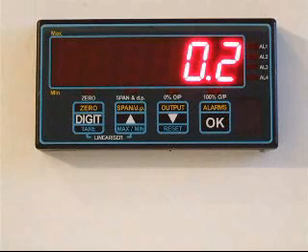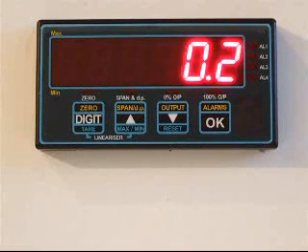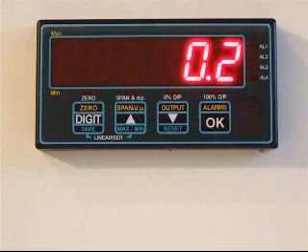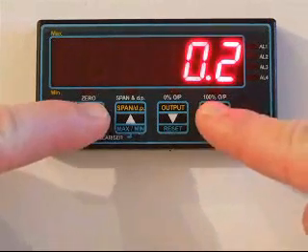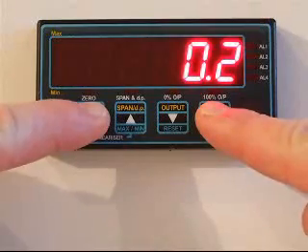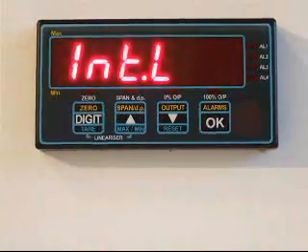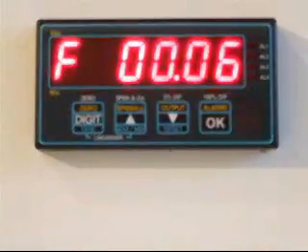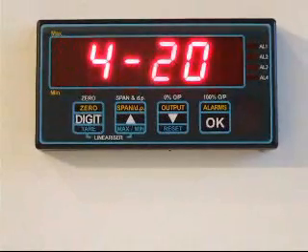Now if I lock the meter and install it and leave it running on site, if I come back and do exactly the same thing, press these two buttons again, I should see that the CAL number is still 15. If it is not 15, that means that somebody has got into the meter and adjusted it.